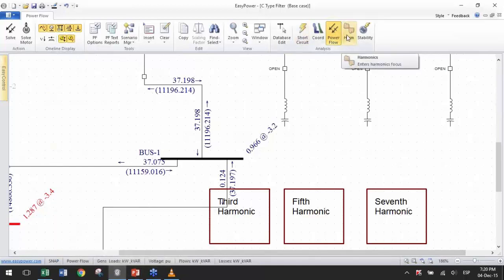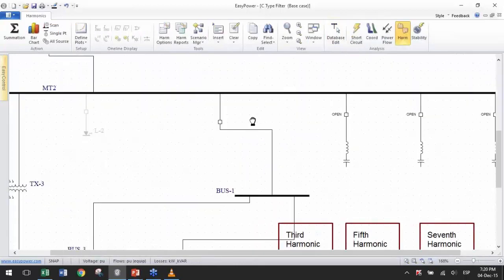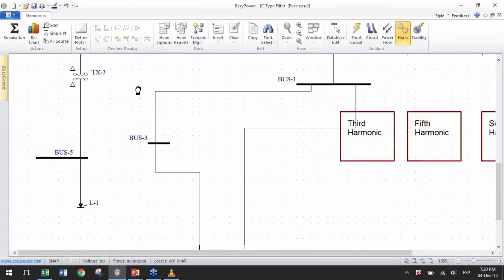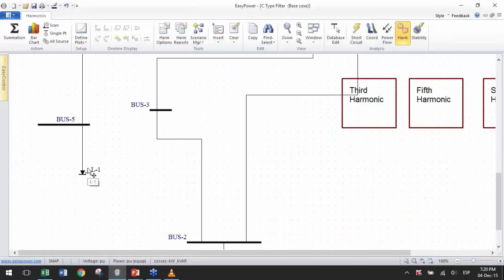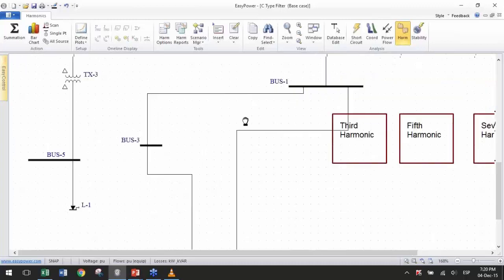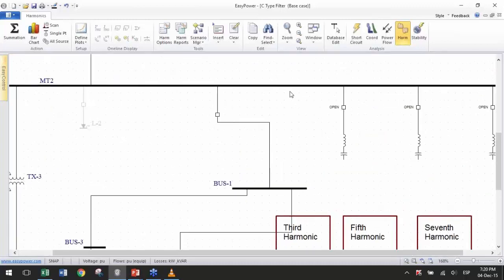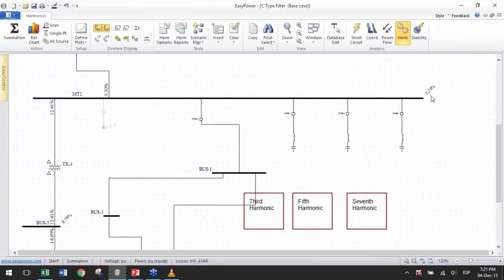Now, what is interesting is when we analyze it from the harmonic point of view. This load has a little harmonic content resembling an electric arc furnace. Again, it's very hard to predict how much harmonic you will have, but it's an estimation. You can estimate a worst case scenario, a best case scenario, whatever works for you. So right now, I think we have a lot of distortion on the bus, 5.24, which is quite high for such a high voltage bus.